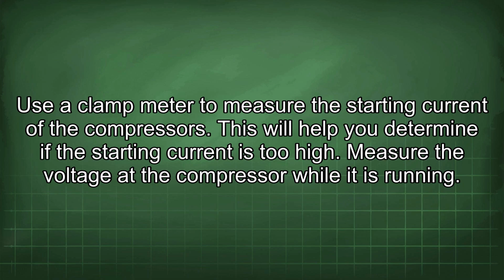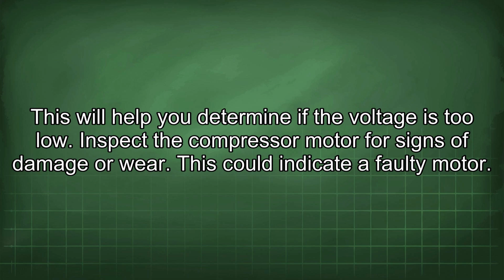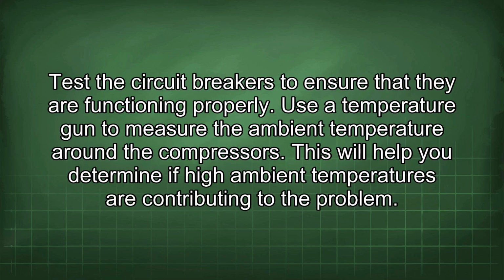Measure the voltage at the compressor while it is running. This will help you determine if the voltage is too low. Inspect the compressor motor for signs of damage or wear. This could indicate a faulty motor. Test the circuit breakers to ensure that they are functioning properly. Use a temperature gun to measure the ambient temperature around the compressors. This will help you determine if high ambient temperatures are contributing to the problem.